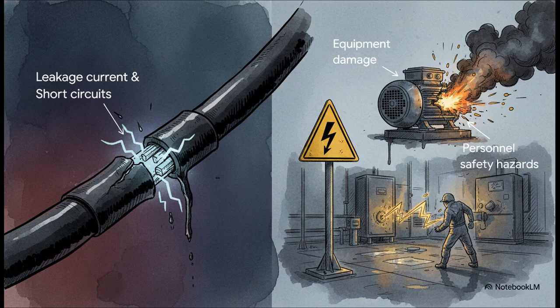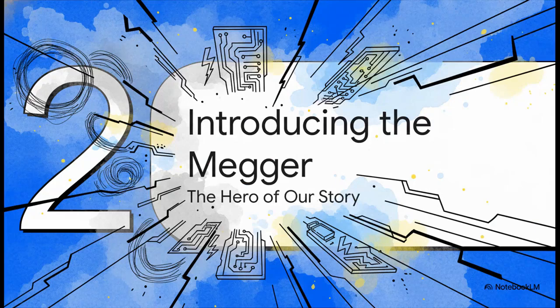See, when that protective insulation starts to break down, it allows for something called leakage current. Basically, electricity escaping where it absolutely should not be. And that can lead straight to short circuits, which can completely fry expensive equipment and, way more importantly, create huge safety hazards for anybody working nearby. So how in the world do you fight an enemy you can't even see? Well, you need a very special kind of detector. So let's meet the hero of our story.